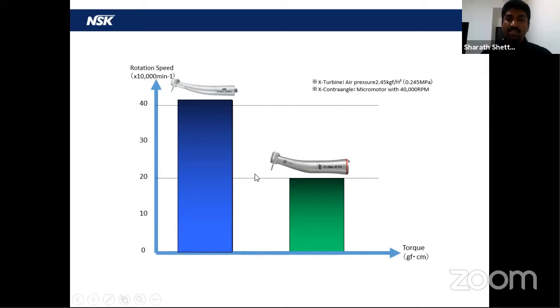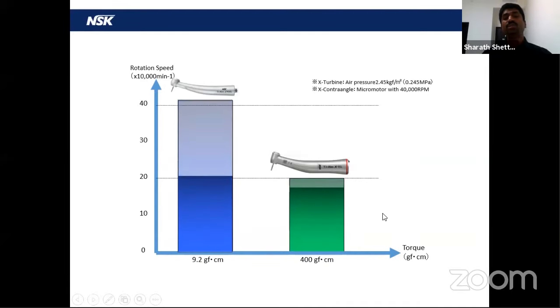But once you touch this particular handpiece on the patient's mouth, the speed will get reduced to half. That is, the aerator handpiece will come down to 2 lakhs RPM, whereas your red ring handpiece, it will just drop a bit, but after that it will remain constant. And if you see the torque, the aerator handpiece will give you 9.2 gravitational force per centimeter, whereas a red ring handpiece will give you 400 gravitational force per centimeter. That means it is 40 times more powerful than your regular aerator handpiece.